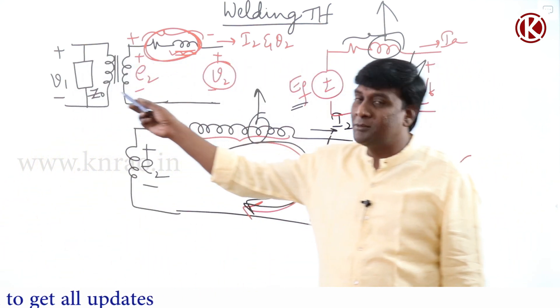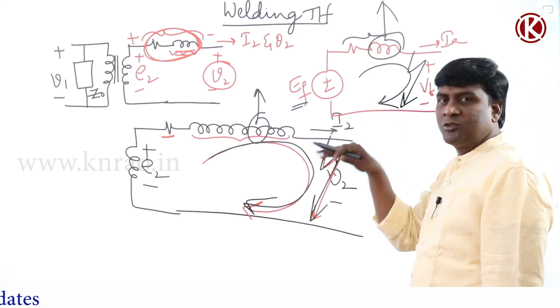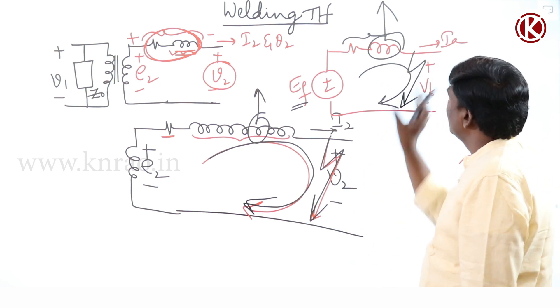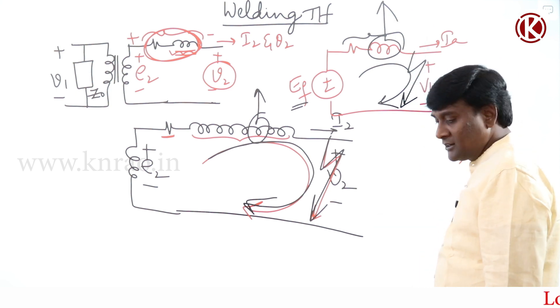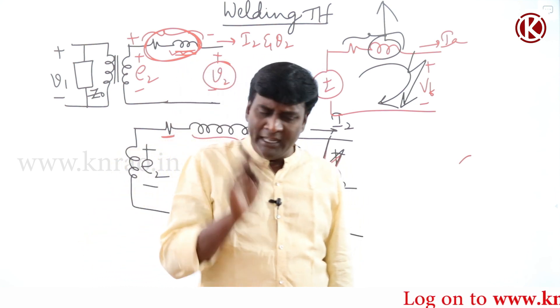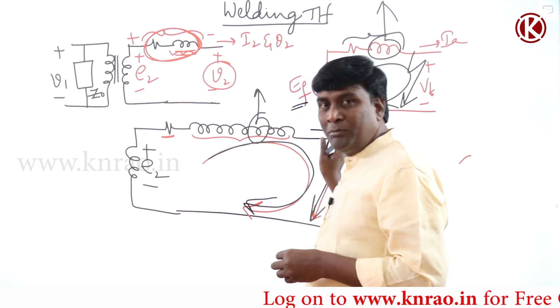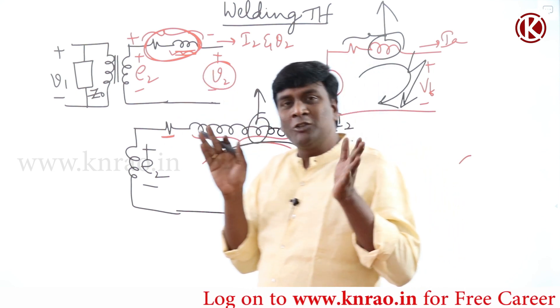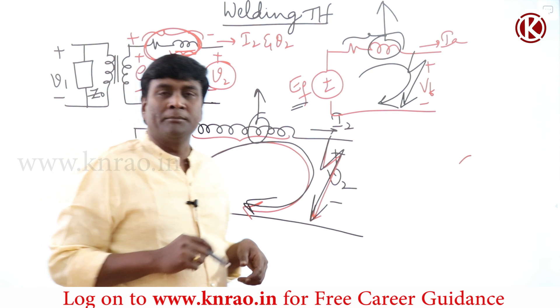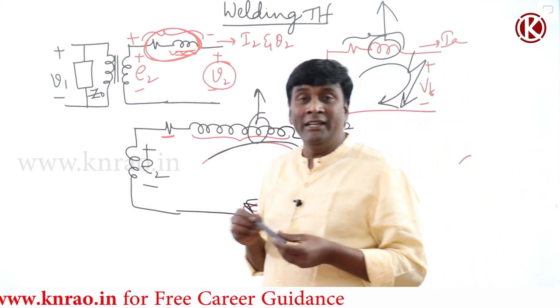So: leakage should be less for distribution and power transformers; leakage should be high for welding transformers. For the alternator, the total x value — leakage plus armature reaction — should be high. Whether leakage should be least or highest depends entirely upon the application. That is why machines must be understood from the perspective of contradictory requirements.